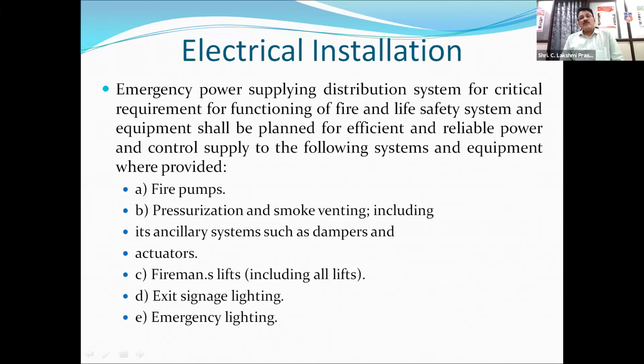Then electrical installations. See, in the majority of fires, electrical short circuit is given as the reason for the origin of the fire. But in some cases it may not be correct. It is very difficult to conclude that electrical short circuit is the real cause, because there may be various other reasons. But in the majority of fires, as we see in the country or elsewhere, the electrical reason is given as the important one. In that, you have overloading, bad earthing practices, loss of insulation, use of non-standard electrical gadgets, and the location of the transformers or oil spilled from the transformer or substations. These are all various reasons for electrical fires.